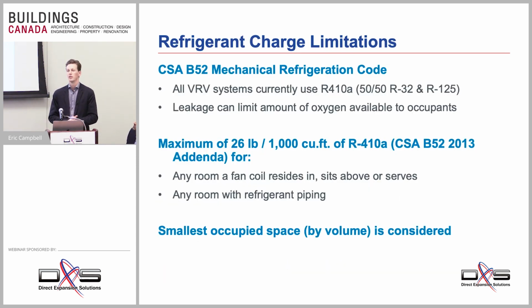I want to talk quickly about refrigerant. So one of the concerns with the VRF or our mini split solution is the refrigerant. It's one of the common concerns. So firstly, all VRF systems in North America currently use R410A. R410A is a non-toxic refrigerant. However, it is heavier than air, so a leakage can limit the amount of air available that we need to breathe. So CSA B52 takes this into account and has come up with a safe limit of 26 pounds per 1,000 cubic feet. And so that's basically the limit. If all of the refrigerant in a system were to leak into one confined space, we need to meet that limitation.